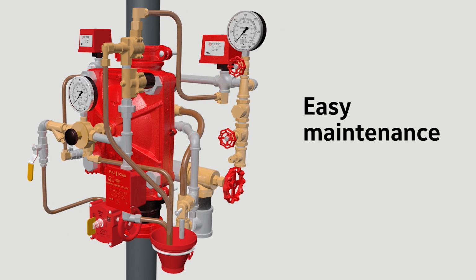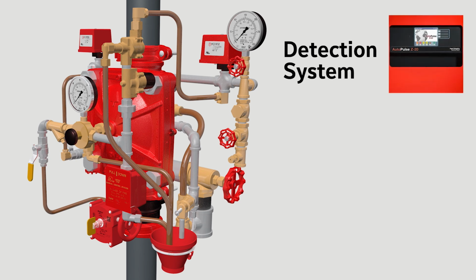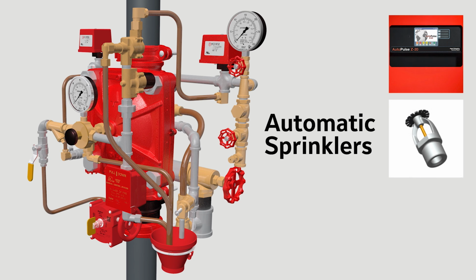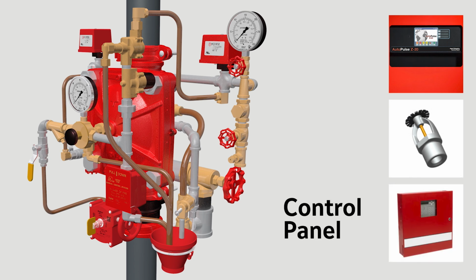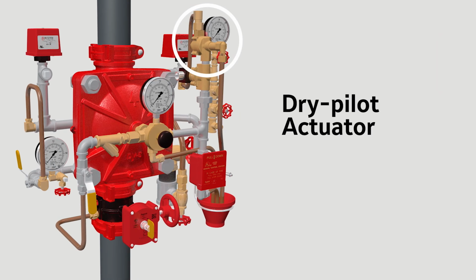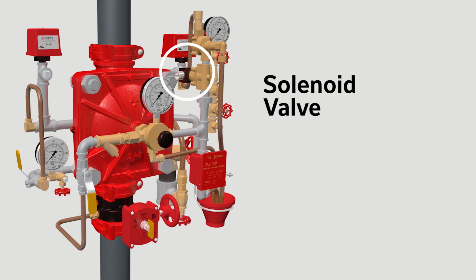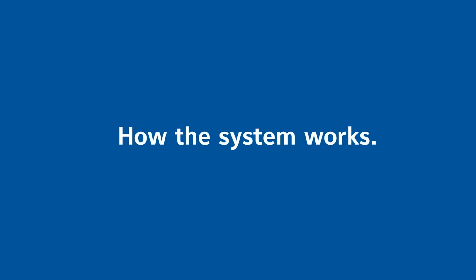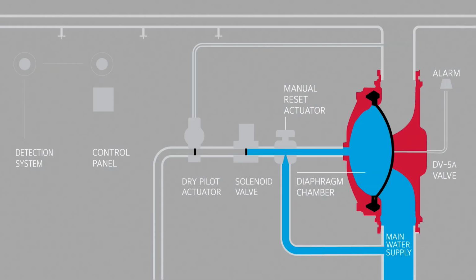The other key components of the actuation system are the electric fire detectors, the automatic sprinklers, the control panel, the dry pilot actuator, and the solenoid valve. Let's look at the system in operation. In the ready position, the sprinkler pipes contain compressed air, while water pressure in the DV5A diaphragm chamber holds the valve closed against the water supply pressure.